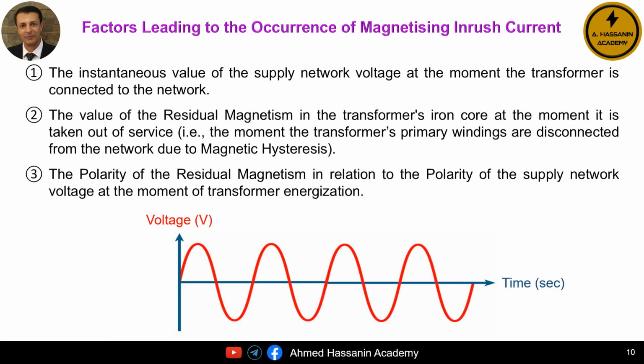The second factor is the value of the residual magnetism or remnant flux in the transformer core at the moment the transformer was disconnected from service. We must note that this factor relates to the moment of disconnection, whereas the first factor relates to the moment of reconnection. The third factor is the polarity between the residual magnetism in the transformer core at the moment of disconnection and the network voltage at the moment of reconnection. That is, whether one is positive and the other negative, or if both have the same polarity.